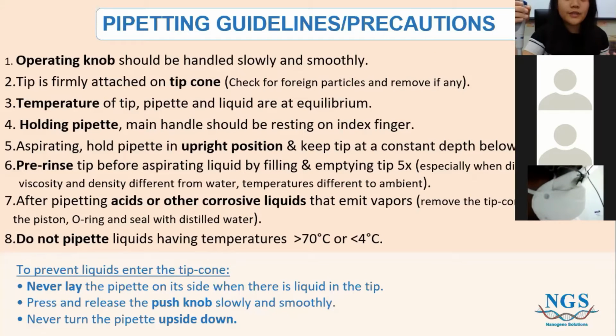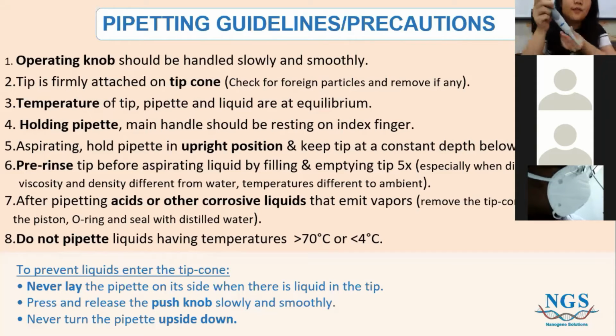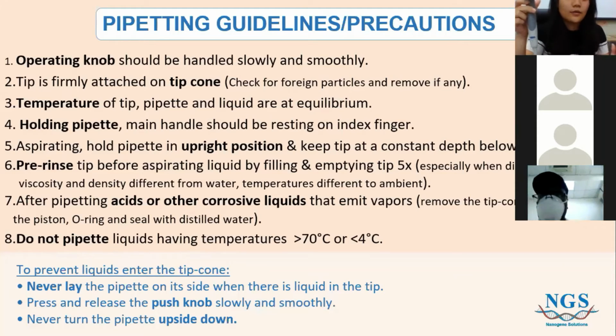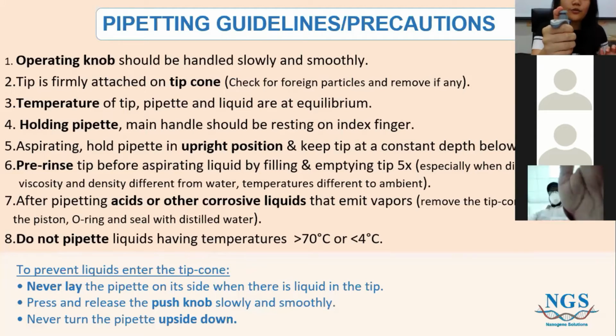As a pipette user, you always want to make sure that your pipette is in good condition, and one way to do that is to never allow water to go into your pipette. How do you prevent liquid from entering the tip cone? Never lay your pipette on its side. Always hang it on your pipette stand or somewhere else. And like I said, when you're operating the knob, make sure that you're doing it slowly and smoothly, and not rigidly. And of course, never turn your pipette upside down.